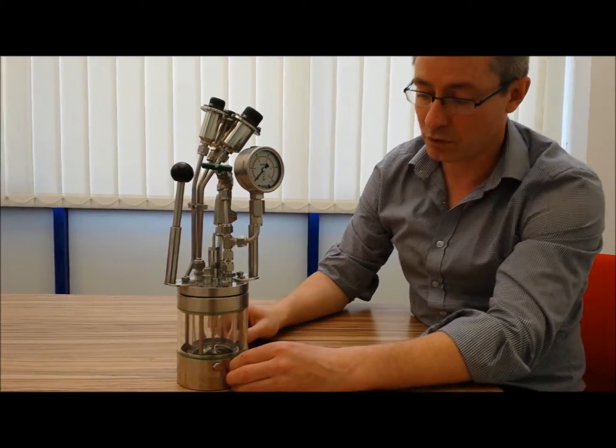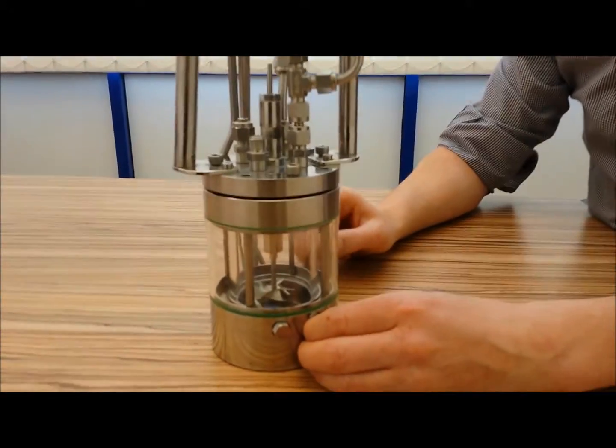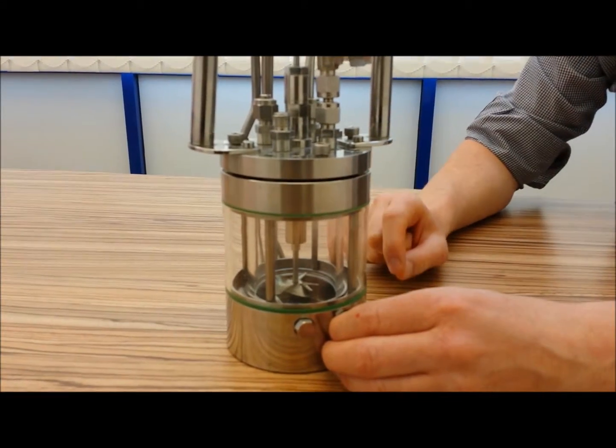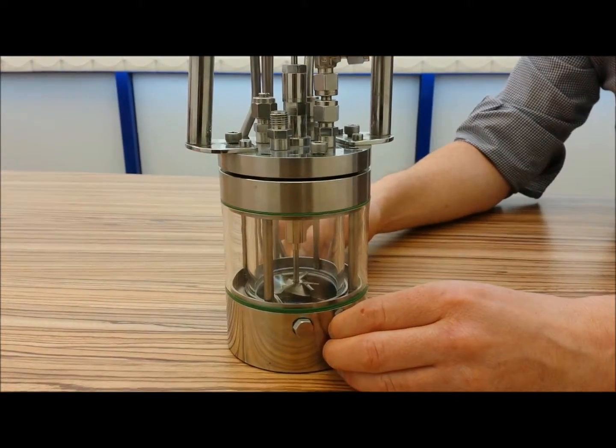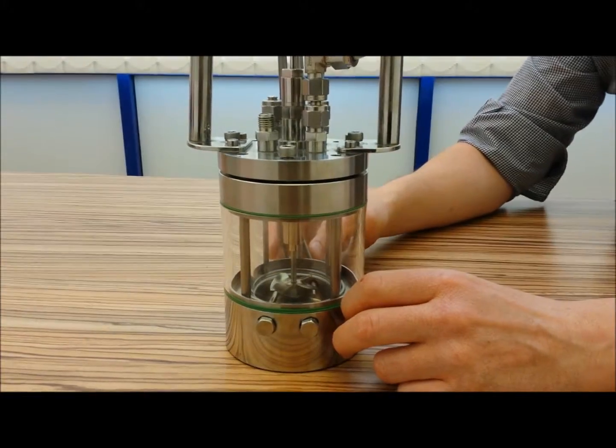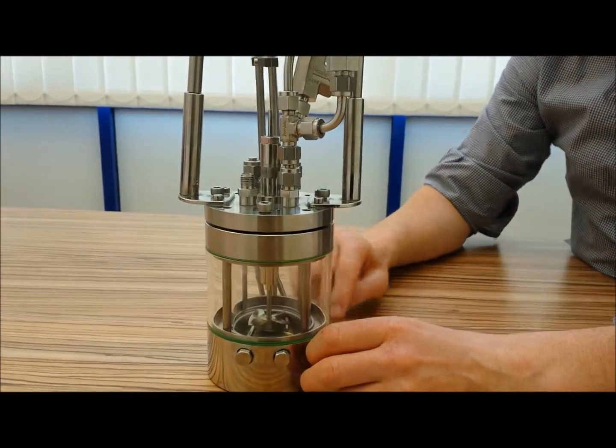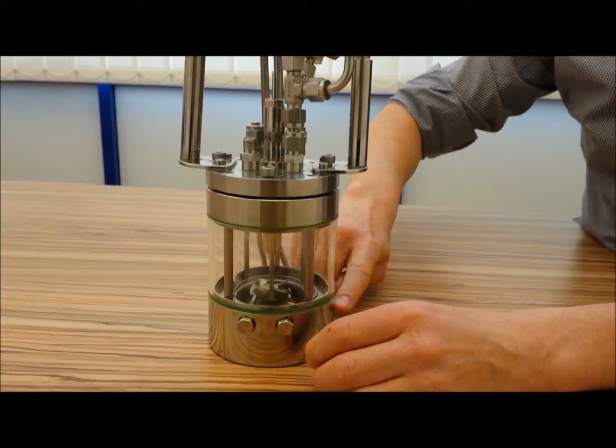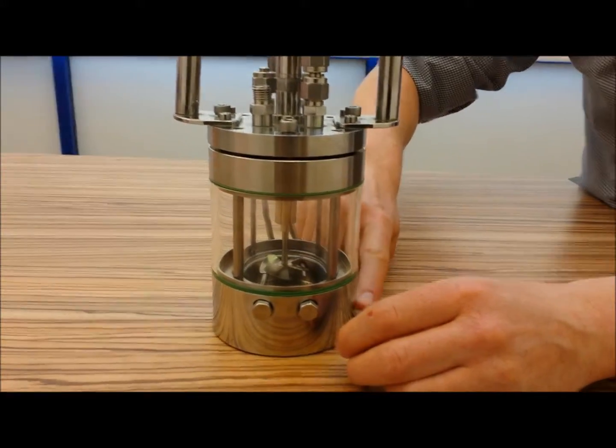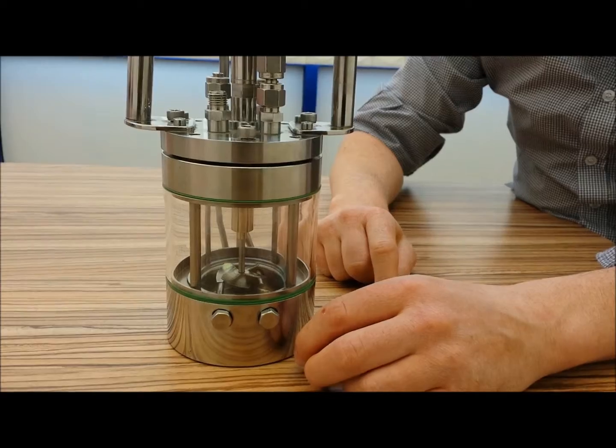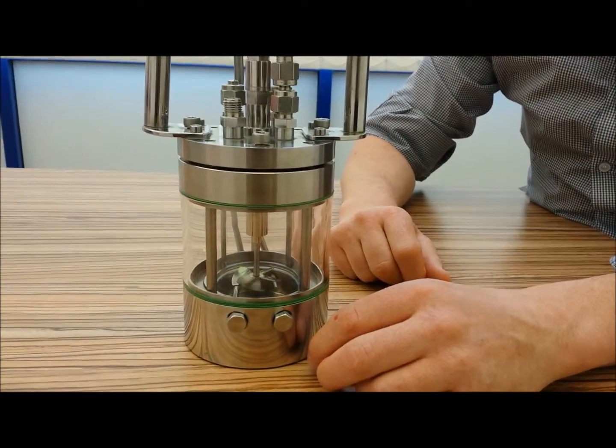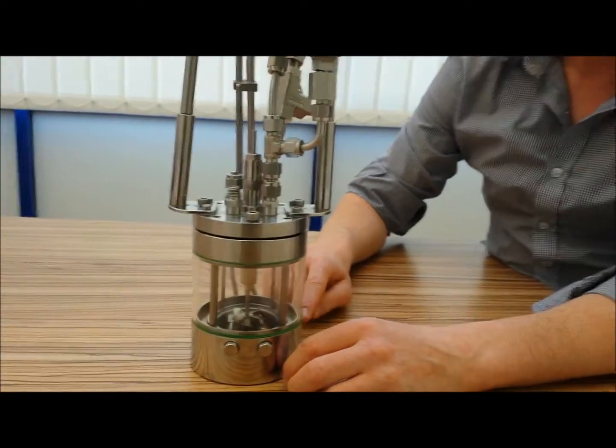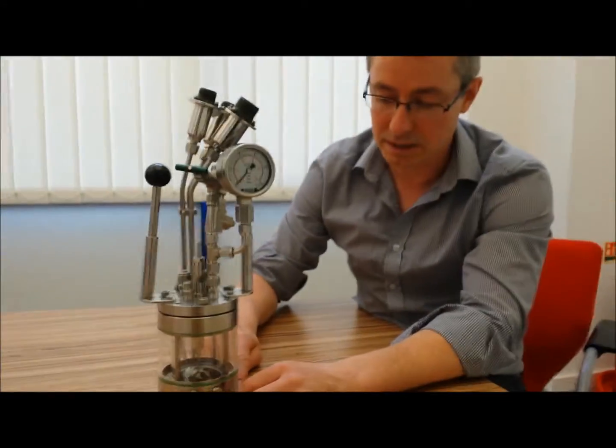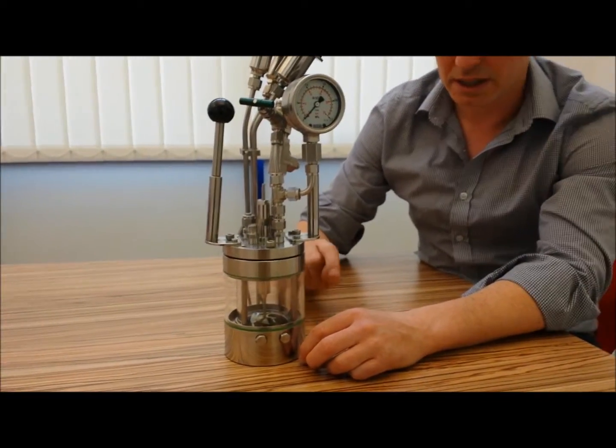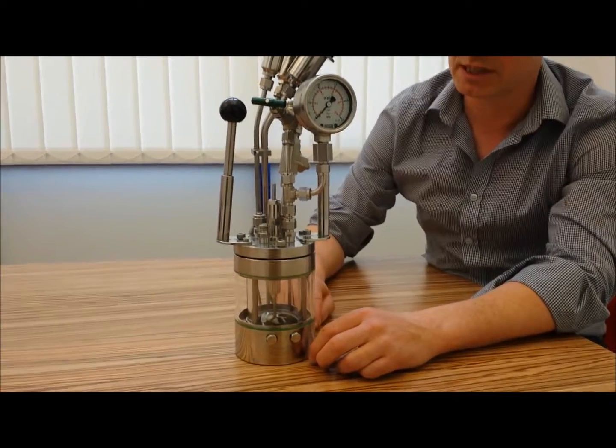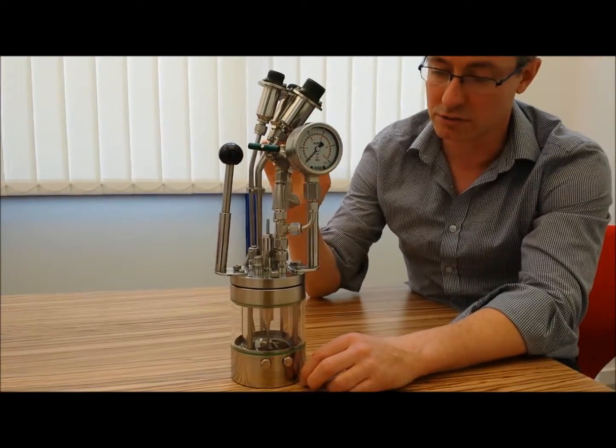One of them is for the internal temperature probe, which we'll be able to see in a bit when we open the lid up. One of them is for the validation heater. This one has one, it's really not necessary. And the third one is for a Peltier heater and transducer that's in the base. So this calorimeter has a unique way of working. We call it true heat flow, and I can definitely discuss that with you. But in order for that true heat flow to work, there's a Peltier in there, and there's a transducer in here, and there's a network of temperature sensors, and so that's what the third electrical connection is for.